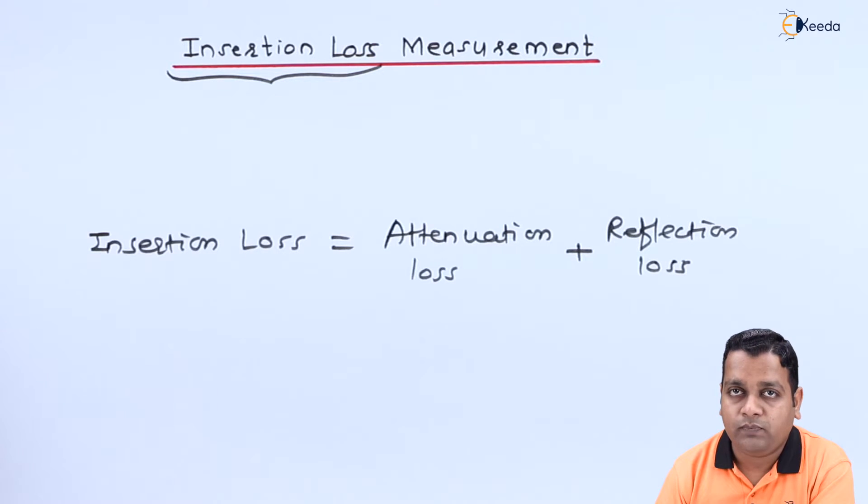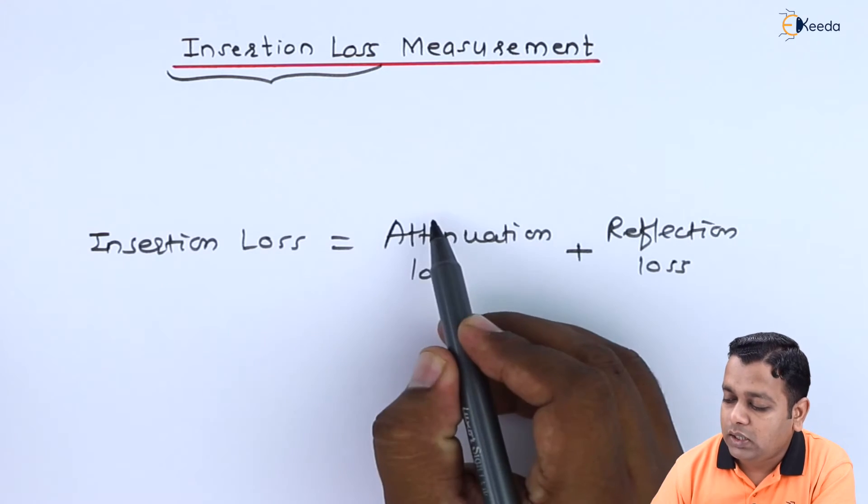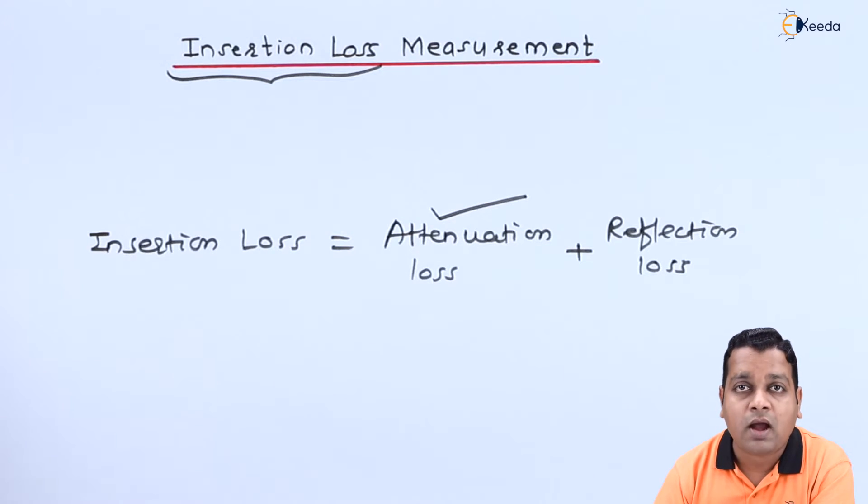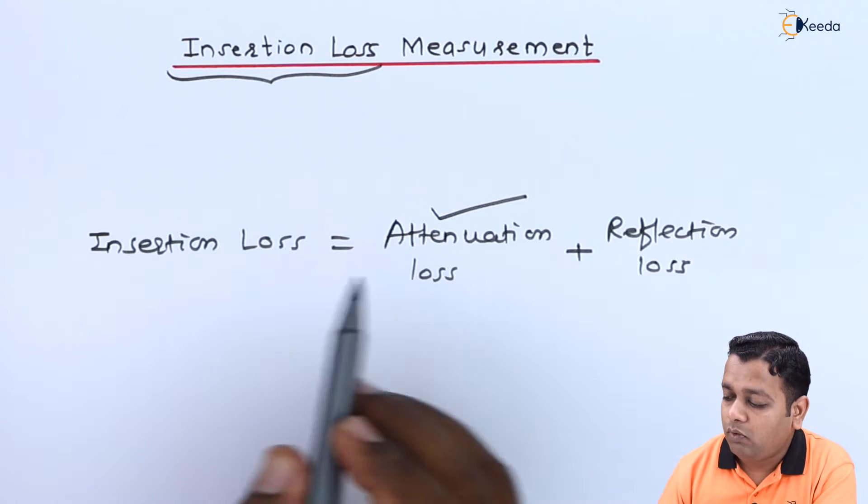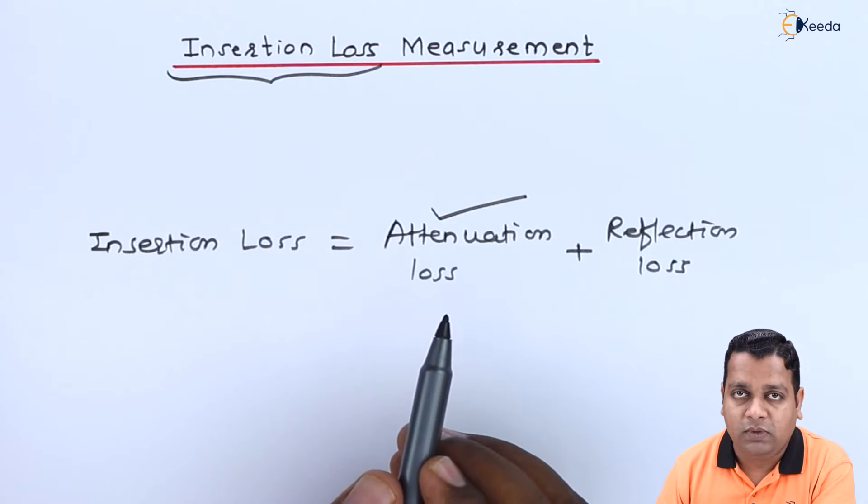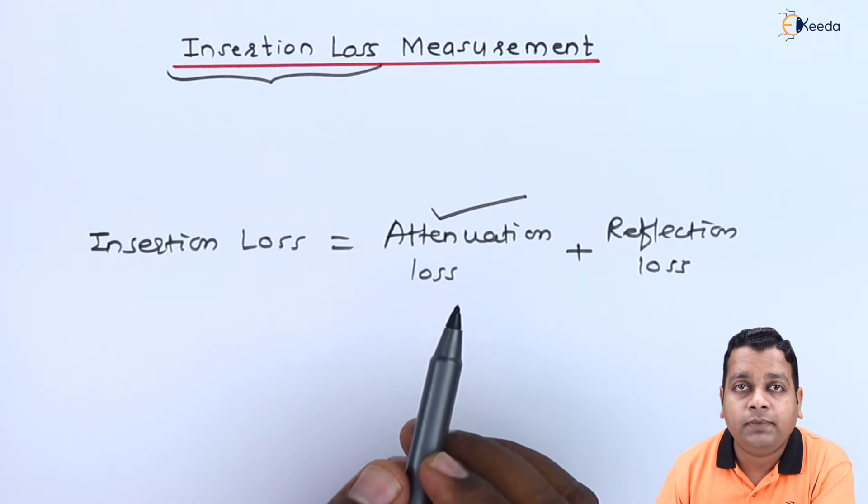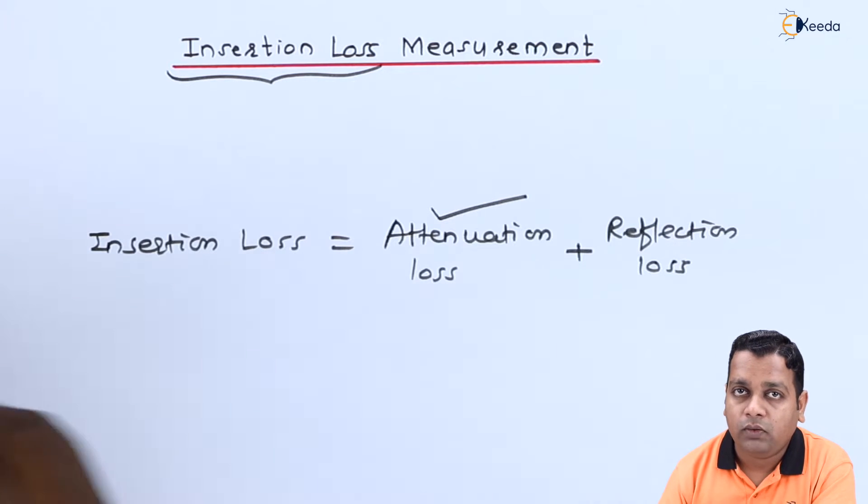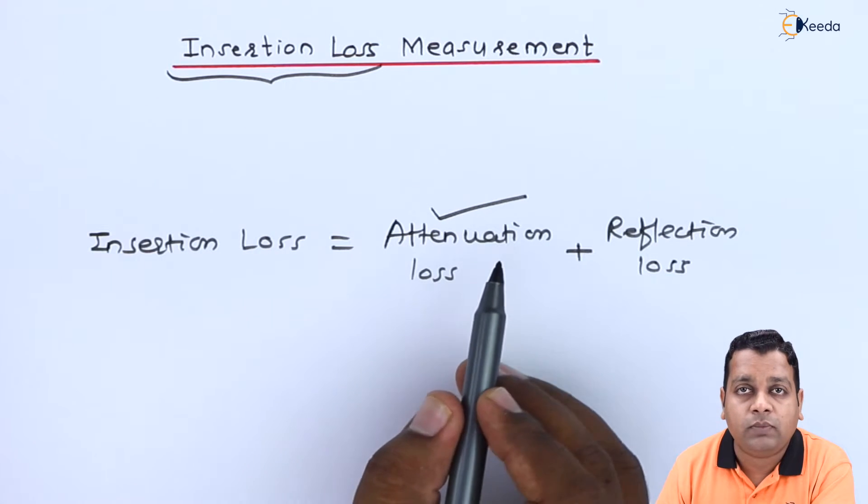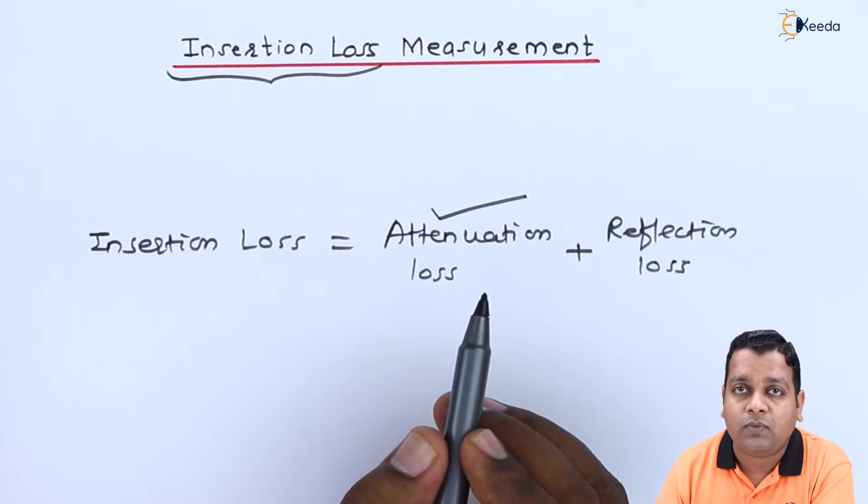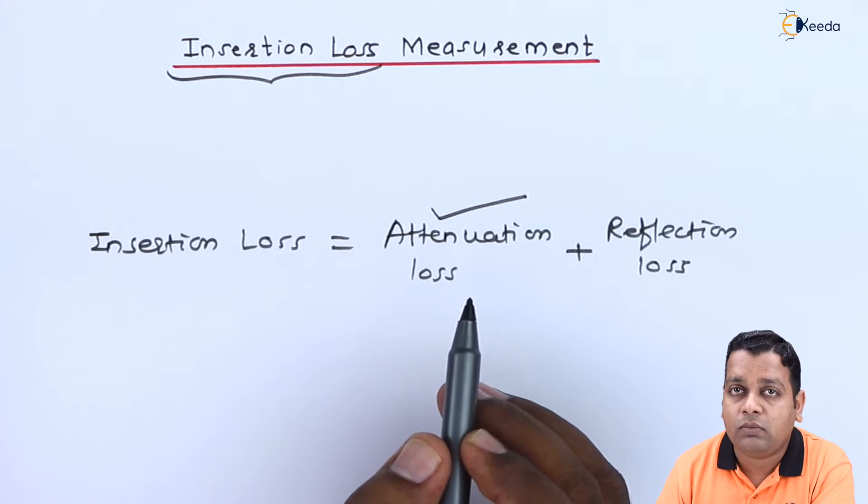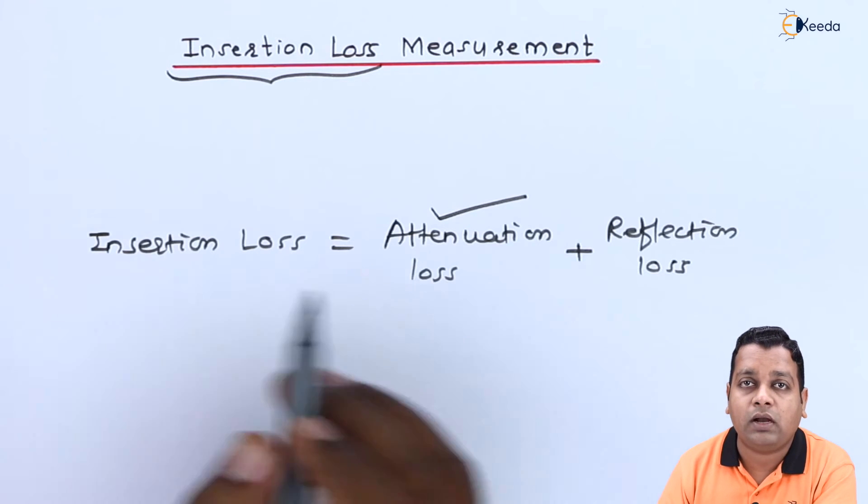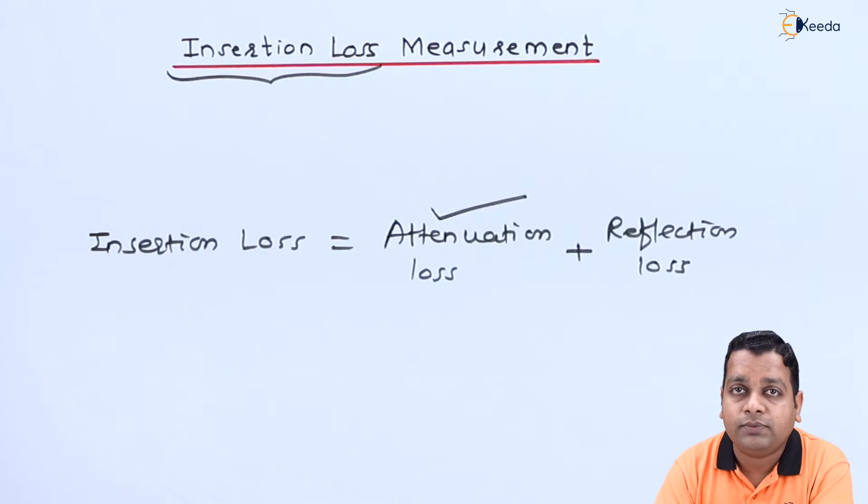Earlier in this chapter, in previous videos, we have gone through attenuation measurement techniques. The power ratio method and RF substitution methods were reported for attenuation measurement. Out of these two methods, the RF substitution method is better because the power ratio method has certain disadvantages that are overcome in RF substitution. Hence, the attenuation loss can be calculated using the RF substitution method.